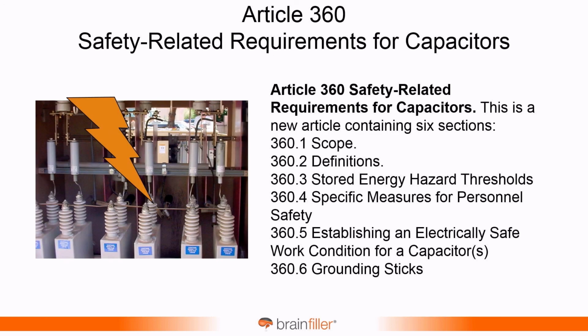Article 360, I mentioned this a moment ago. Brand new. Capacitors were only referenced a couple of times historically in NFPA 70E, but they are a large source of stored energy and quite a source of potential hazard. And so there is a new article, actually quite large, that is broken up into scope, definitions, and then the stored energy hazard. That's really important. And measures for personal safety, establishing an electrically safe work condition that's specific for capacitors. It's not like what we'll call a traditional electrically safe work condition. There are other considerations that need to be made, and the use of grounding sticks.